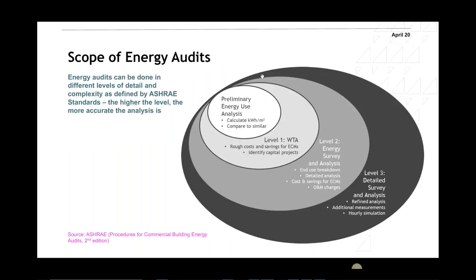What's the scope of energy audits? Energy audits can be done in different levels of detail and complexity as defined by ASHRAE Standard 211. The higher the level, the more accurate the analysis is, the more time is required, and the more costly the IGA or the audit becomes.